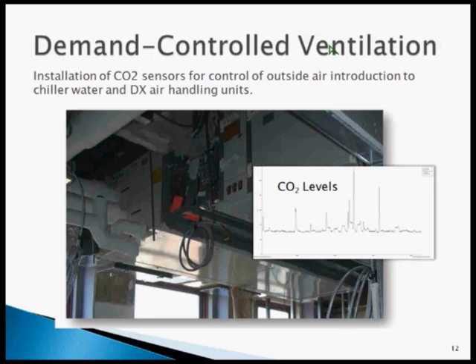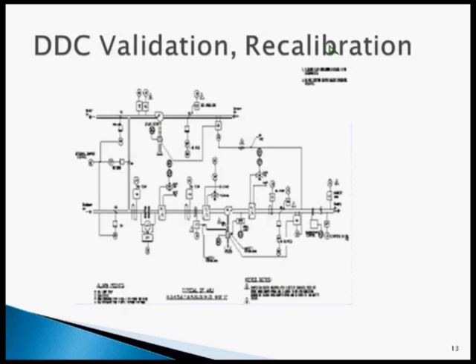Very low cost for the benefit. Very low cost. And the CO2 monitoring systems are getting more and more reliable, sophisticated, as long as you do calibration on a regular basis, so you've got an actual system maintaining. And this, from a safety point of view, makes more sense because you're actively controlling it. You're not just saying, like Tom said, 100 square feet per person. You're guessing. This is an actual way to control ventilation.